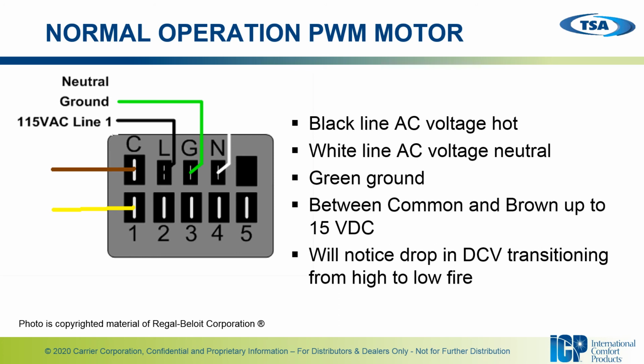Normal operation readings on the variable constant torque motor: naturally, between your black line and your white line you should see 120 volts, with green being your ground. However, during normal operation, between the common and the brown, you should see up to 15 volts DC. Now you will have to take this measurement back to the common on the control board. You will notice a drop in the DC voltage transitioning from high to low fire on the furnace because it will effectively change speeds.